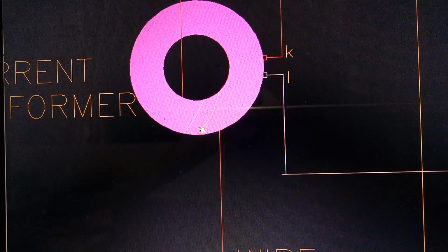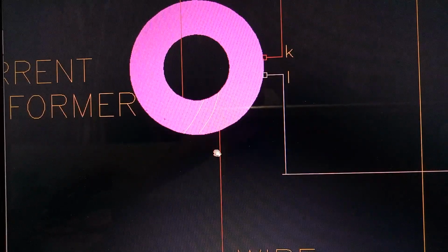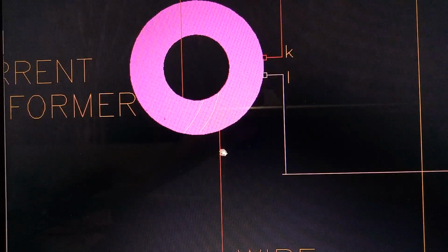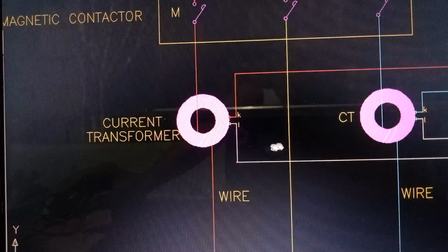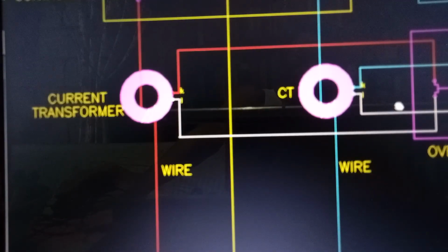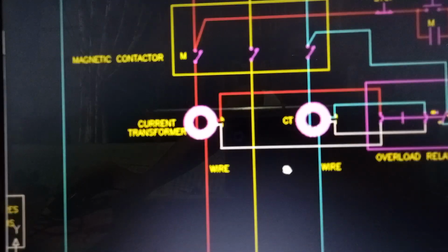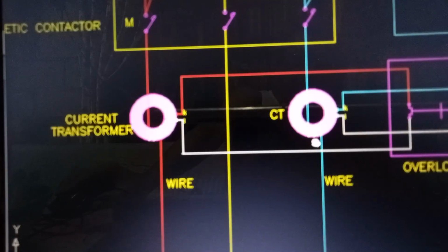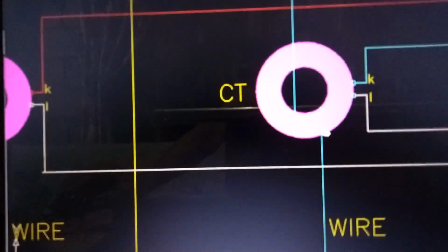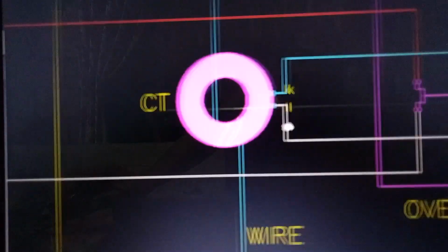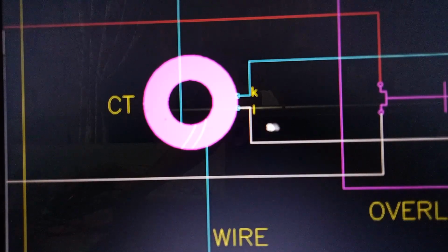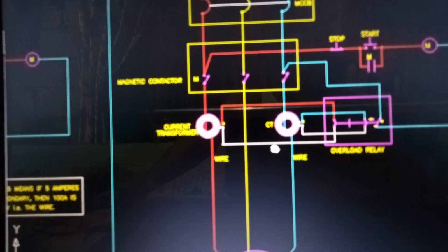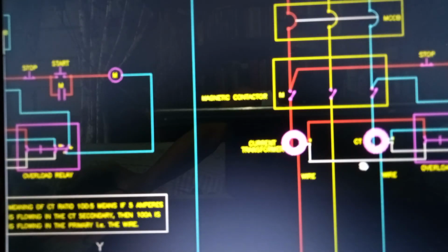So the purpose of this scheme of using a CT and then wrapping the branch circuit wire through the hole of the CT 2 times is to increase the current going to the overload relay. In this case, if the current to the motor is very small, you can wrap the branch circuit wire to the current transformer in order to increase the current that will reach the overload relay. So this is the purpose of using a CT, current transformer, in the full voltage magnetic starter.